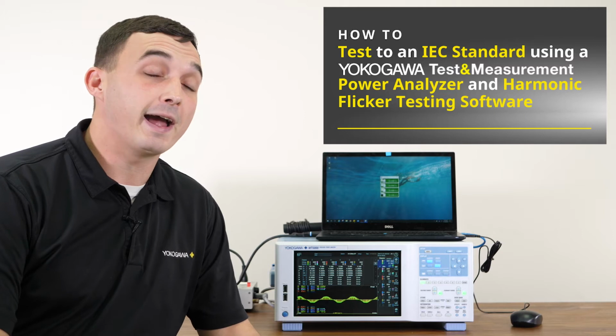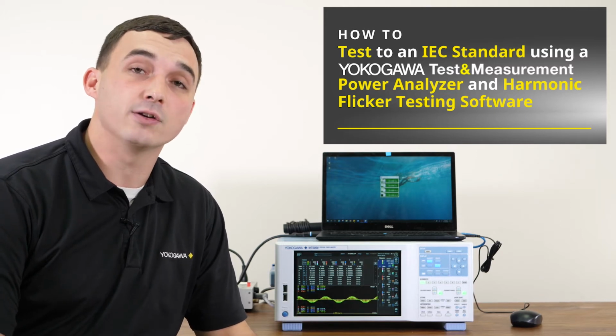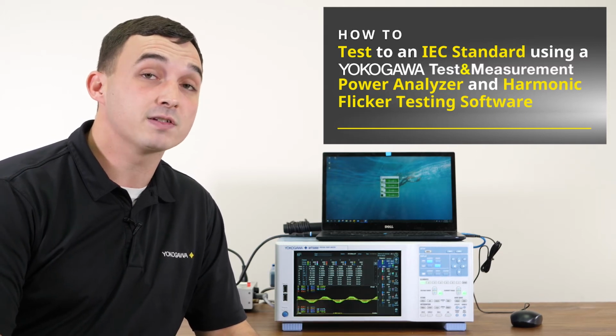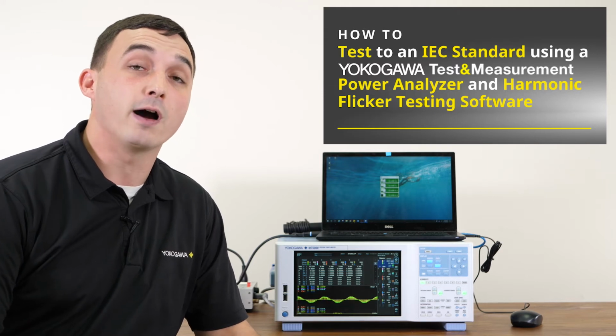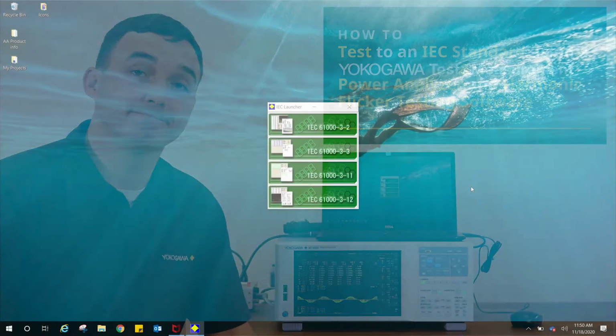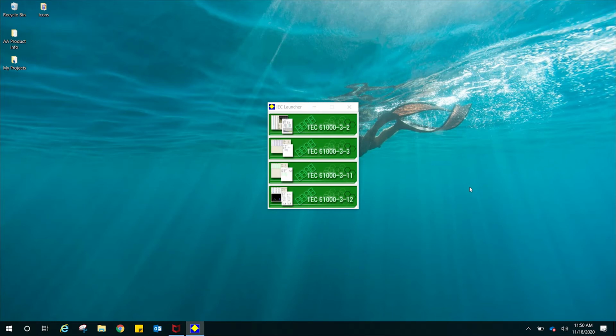Today we're going to talk about how to test to an IEC standard using a WT5000 Precision Power Analyzer and the Harmonic Flicker testing software. Yokogawa's Harmonic Flicker measurement software enables engineers to test to several IEC 61000 standards using the WT5000 Precision Power Analyzer. The software automates the process of judging if the device under test is compliant with the chosen standard and also allows you to output the necessary test reports for your records.